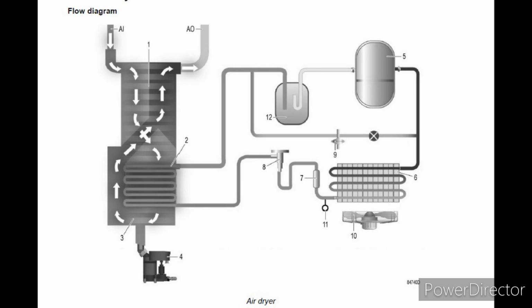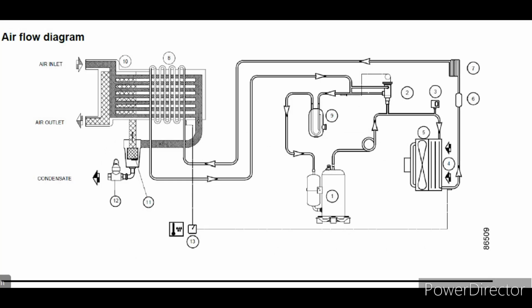Compressed air enters the heat exchanger and is cooled by the outgoing cold dry air. Water in the air starts to condense, then the air flows through the heat exchanger evaporator where the refrigerant evaporates. This cools the air further, close to the evaporating temperature of the refrigerant, and more water in the air condenses. The cold air flows through the separator where all the condensate gets out. The condensate is automatically drained through the outlet. The outgoing cold dried air flows through the heat exchanger where it is warmed up by the incoming compressed air. I am only explaining this air circuit, so look at this air circuit diagram. What I explained is only the compressed air circuit diagram, the airflow diagram.